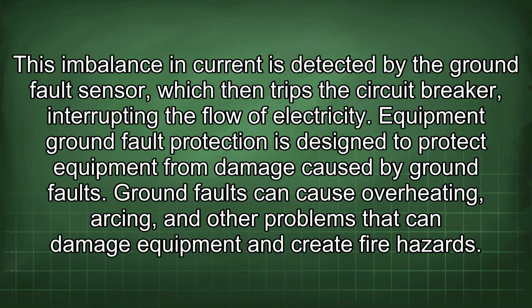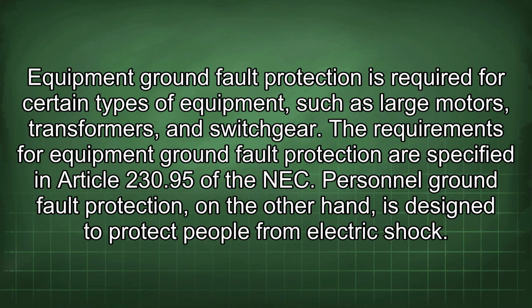Equipment ground fault protection is designed to protect equipment from damage caused by ground faults. Ground faults can cause overheating, arcing, and other problems that can damage equipment and create fire hazards. Equipment ground fault protection is required for certain types of equipment, such as large motors, transformers, and switchgear. The requirements for equipment ground fault protection are specified in Article 230.95 of the NEC.